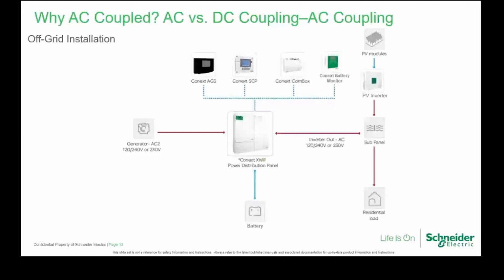So in off-grid installations, basically you've got no grid. You're going to have a generator, and then you can have some peripheral equipment, say the AGS, system control panel, ComBox, or Conext battery monitor. And you have the PV inverter located on the load output side of the XW. And then that goes directly to the sub panel, then goes directly to the residential loads.